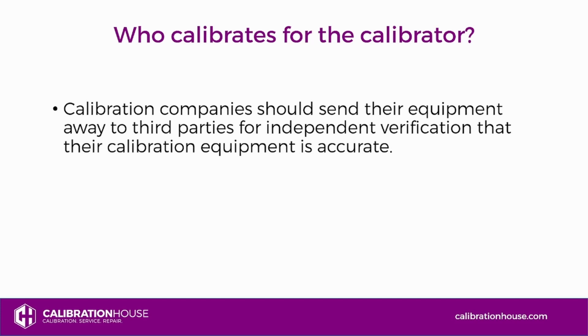So who calibrates for the calibrator though? So calibration companies should send their equipment away to third parties for independent verification that their calibration equipment is accurate.